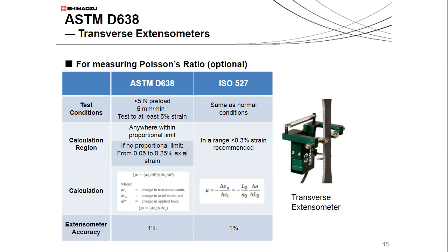They both have the same extensometer accuracy requirements, which can be achieved, as I mentioned, with our video extensometer or with a contacting transverse extensometer, such as the one pictured.